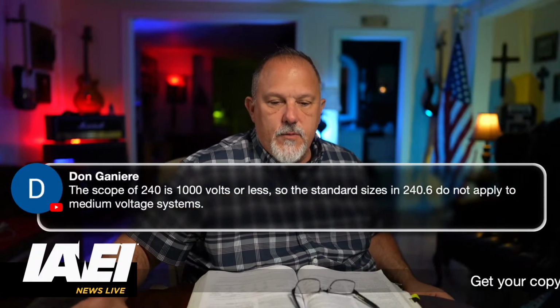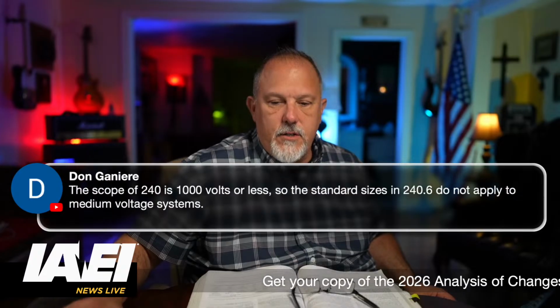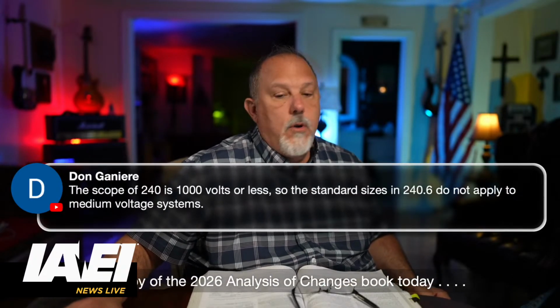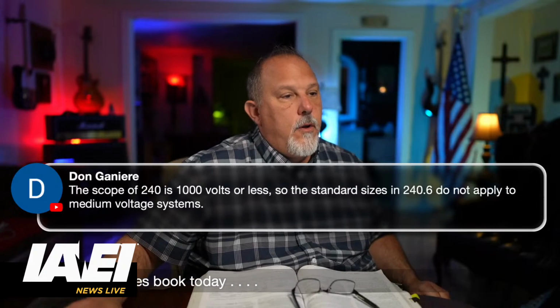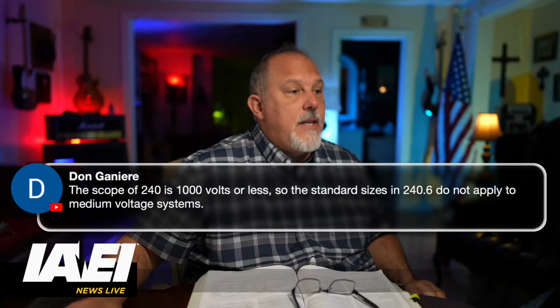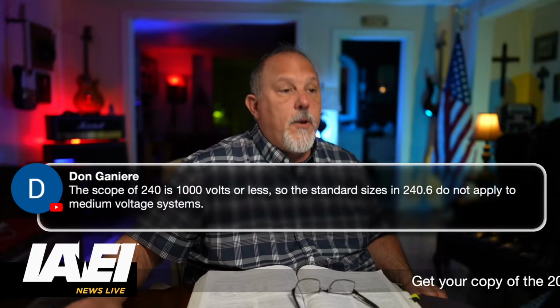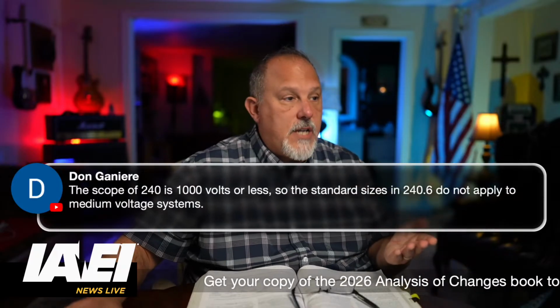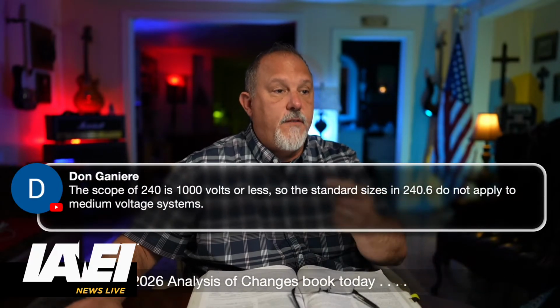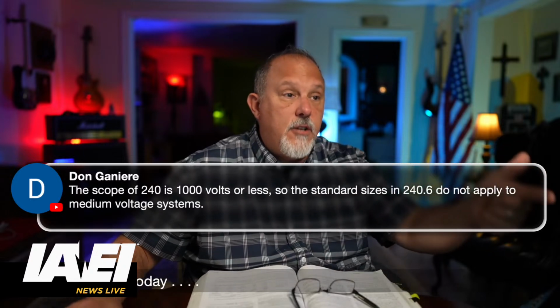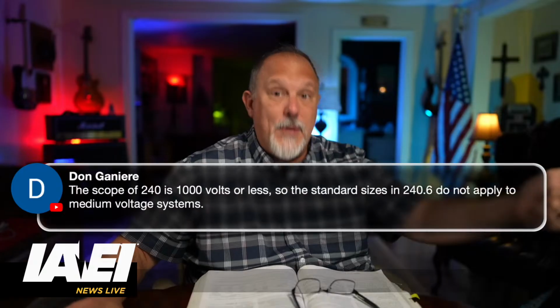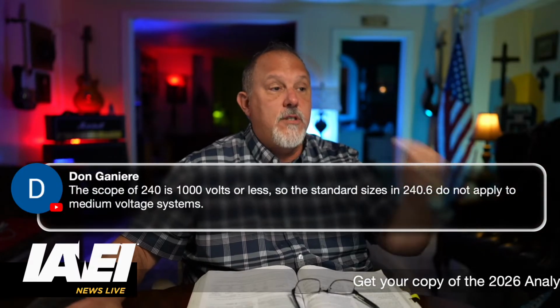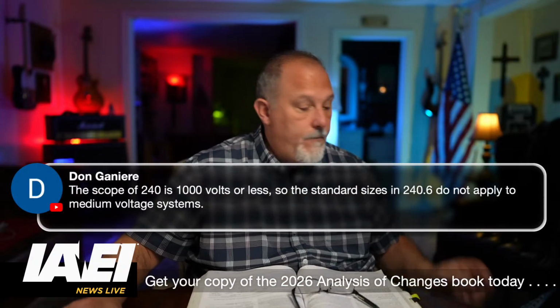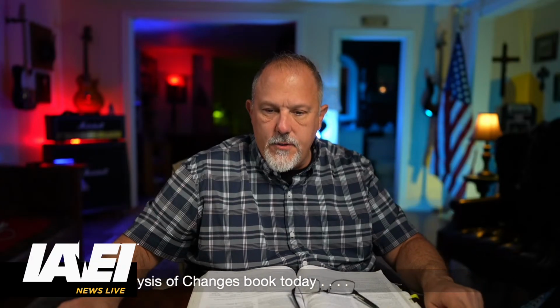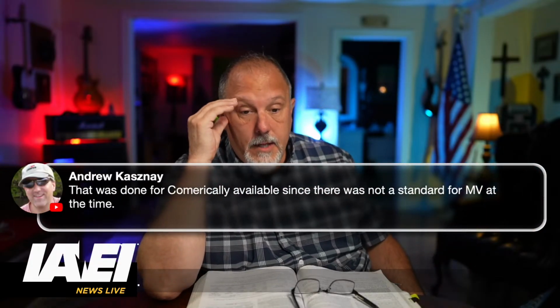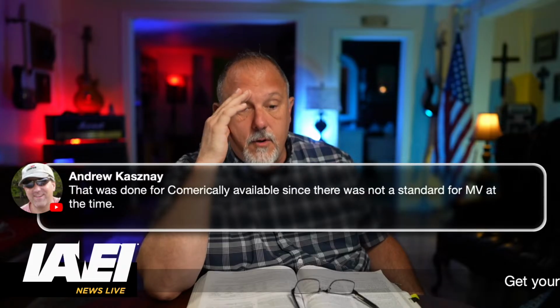The scope of 240 is 1,000 volts or less, so the standard sizes in 240.6 Yeah, well, that's what it says. It says the next higher standard rating or setting for fuses and circuit breakers 1,000 volts and below. And then item 2 says the next higher commercially available rating or setting for fuses. So even if there was a table in 240 that applied, it wouldn't apply because you have to use the next commercially available fuse or rating. Andrew says that was done for commercially available since there was not a standard for, oh, that's right, exactly.